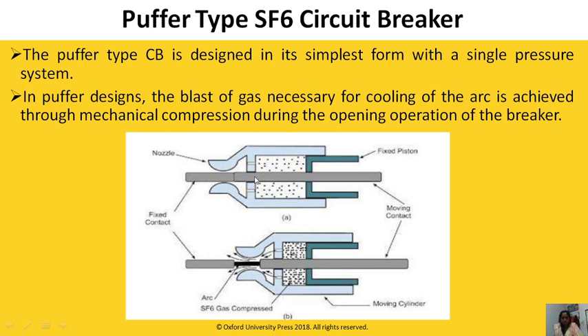In the puffer type, there is a fixed contact and a moving contact, initially in the closed position. After a fault occurs, the relay gives a tripping signal and the circuit breaker contacts open. As the moving contact separates and moves away from the fixed contact, it compresses the gas inside. The pressure reaches 14 kg per centimeter square, and that gas blast is directed onto the arc, causing it to be quenched.